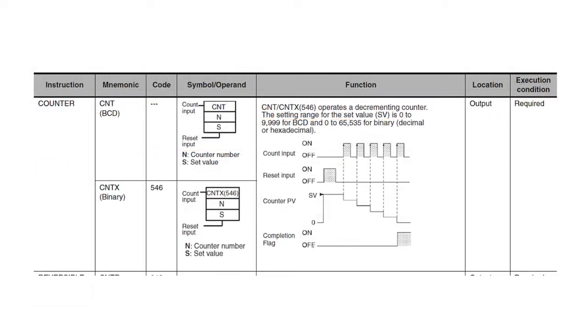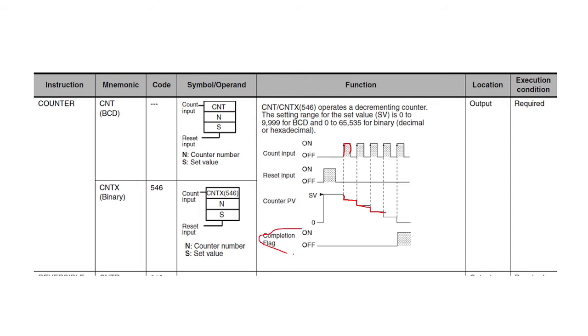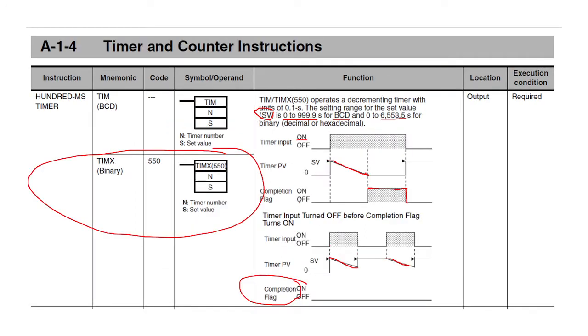For a counter, this is slightly different. For a counter, each pulse is counted from the set point and decrements value by 1. After it's counted down to 0, the complete flag will come on. Another slight difference here is you must give it a reset input to reset the counter so it can be used again, unlike the timer here, where it's reset when the timer finishes.